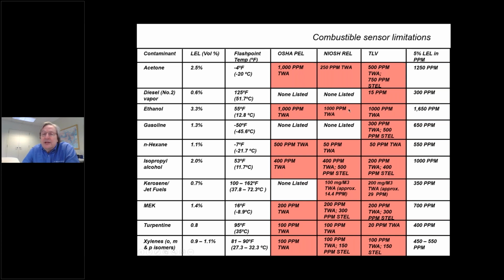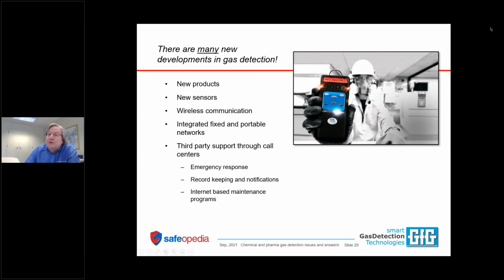And if you look at ethanol, ethanol is a good example. The OSHA-PEL, the NIOSH-REL, and the TLV are all 1,000 parts per million. If you set the LEL alarm for ethanol to go off not at 10% LEL, but at 5% LEL, that would be 1,650 ppm. Well, that's going to be higher than the TWA limit. If you set it to go off at 20% LEL, then that's over 300% higher than the toxic exposure limit. That's too high. So for all of these VOCs, every one of them, where you have a published exposure limit, you're going to exceed the toxic exposure limit before you get to the 10% LEL or even 5% LEL.